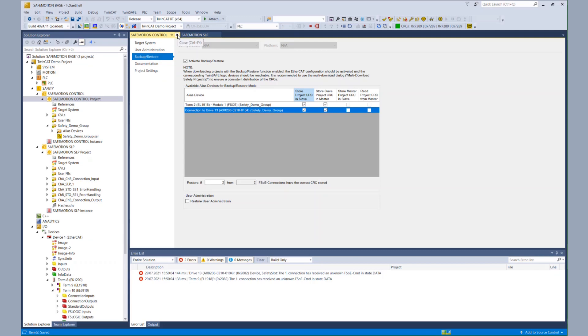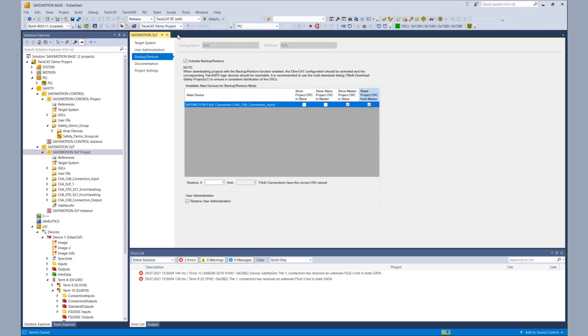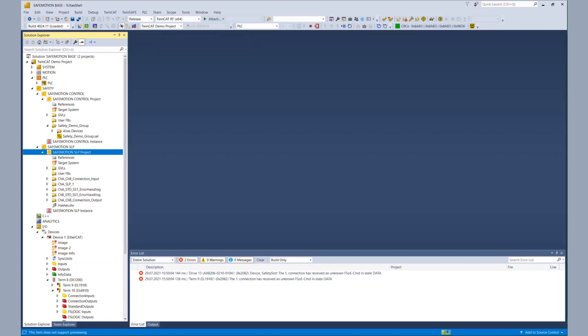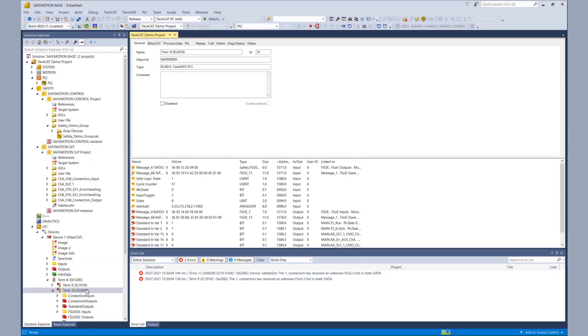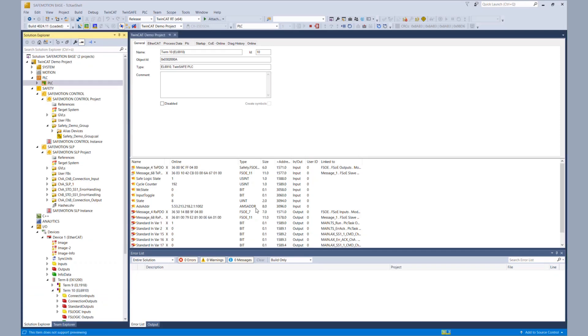Before we go to the usage of the TwinCAT 3 backup and restore library, we check if the download worked and both safety projects are running. We go to the process image of the EL6910 and see that the two connections to the EL1918 and the AX8000 are running as expected.